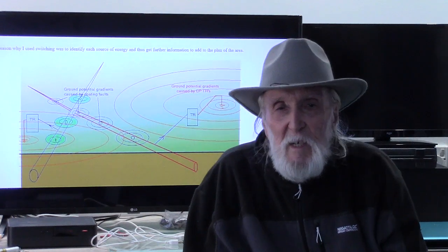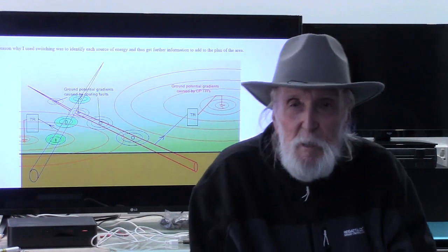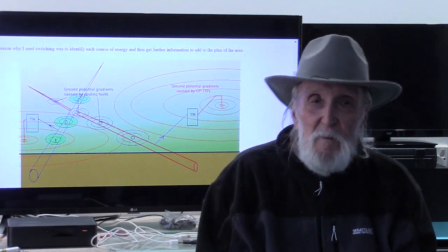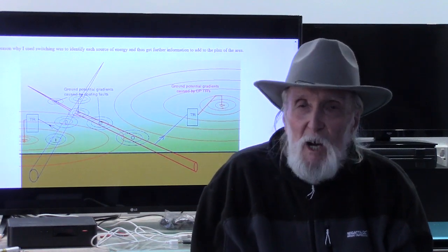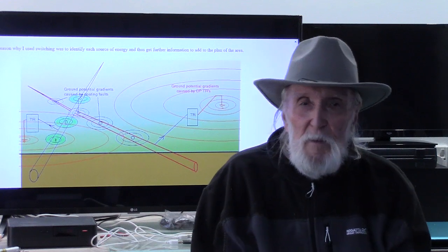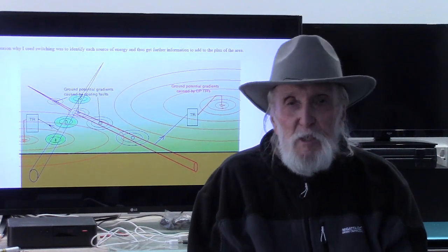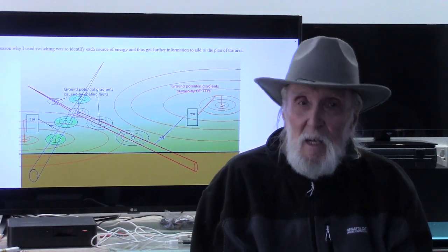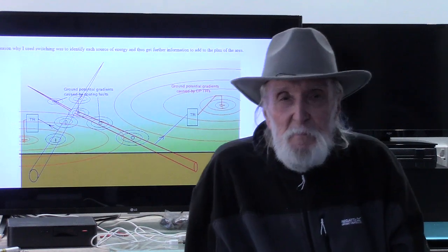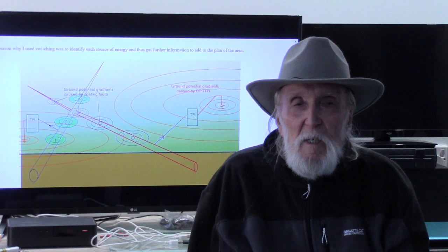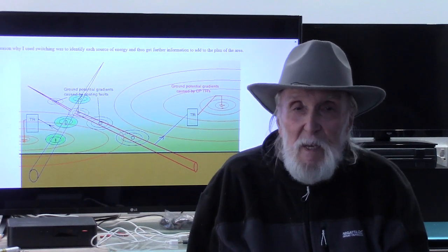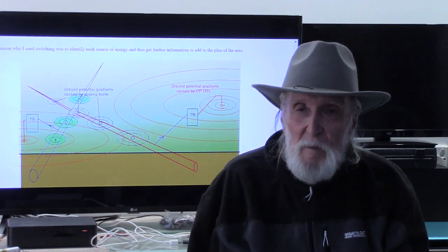A foreign conductor passing through the subject ground bed area, very green, will pick up charges and discharge in areas where the ground bed potential is lower, shaded red. Their presence will cause the ground potential to be higher, greener or less red than the surrounding ground.